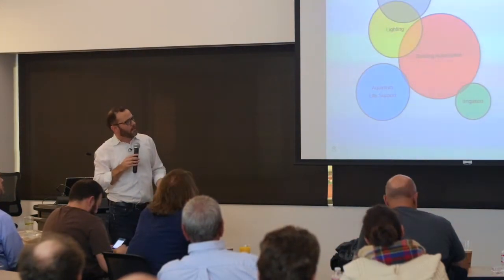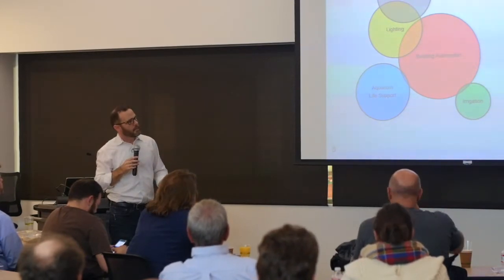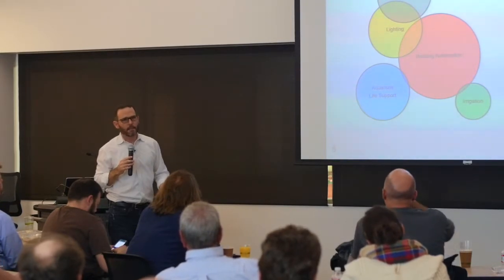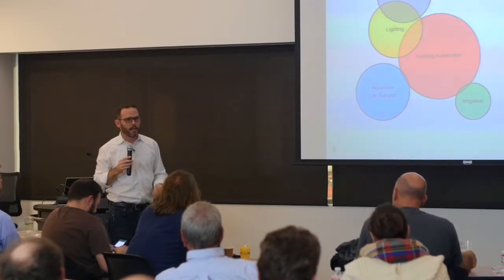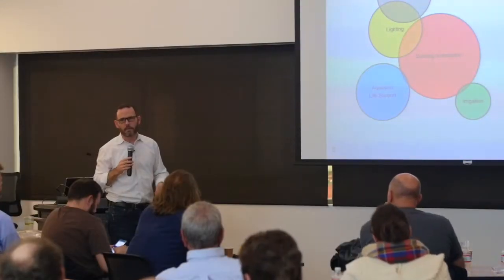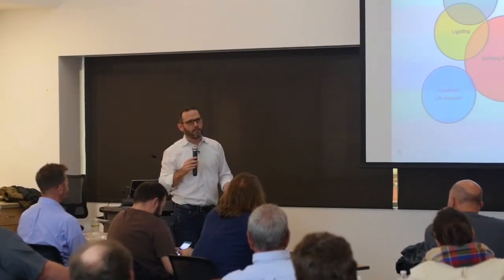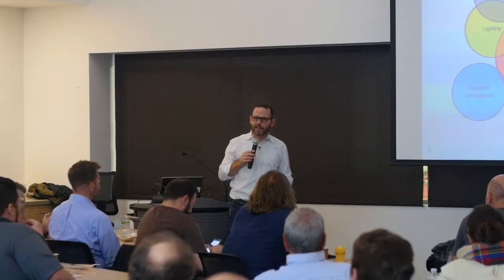Fire life safety is standalone in California. It's not allowed to be integrated. So the fire life safety was an Edwards system, managed by an external contractor, as many are. But that's pretty specific to California. I know in other states, like in Nevada, you can have it integrated with building automation, and typically are. But in California, you can't do that. You can't even have a serial output to the building automation system for logging. So the logging was basically a print spool. Hopefully they'll update that at some point, but California, I think, has a lot of momentum.